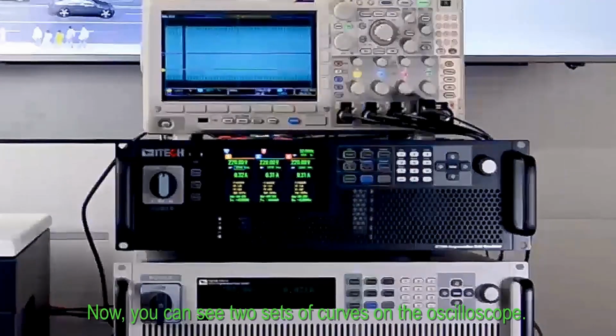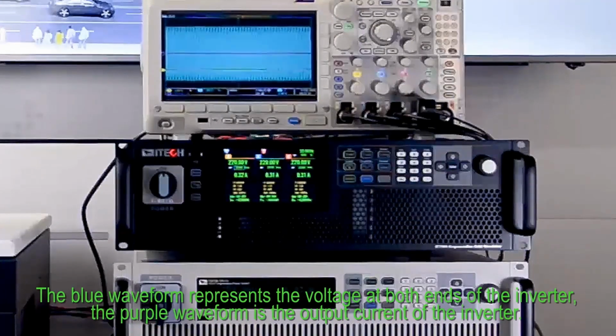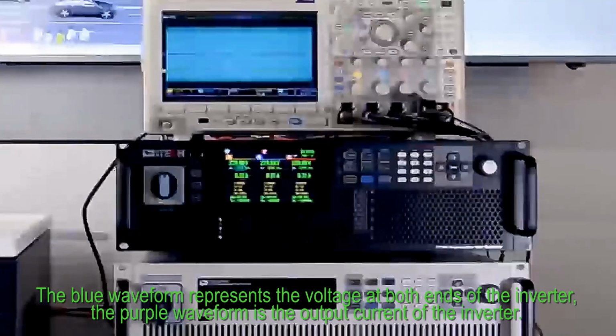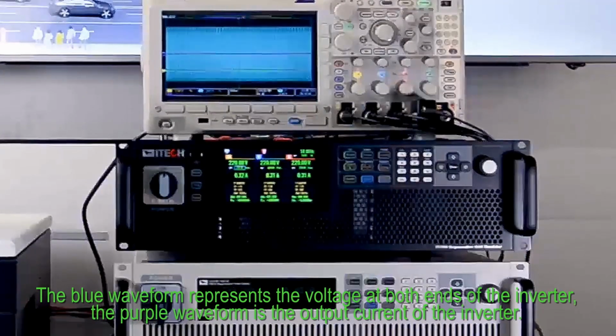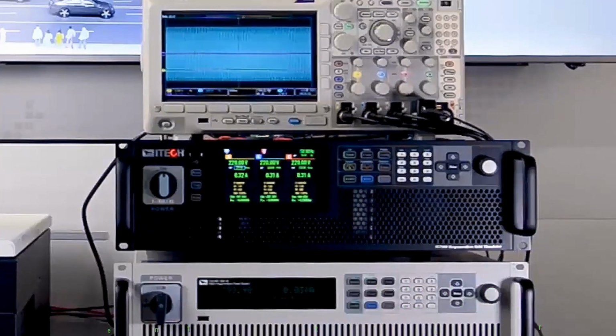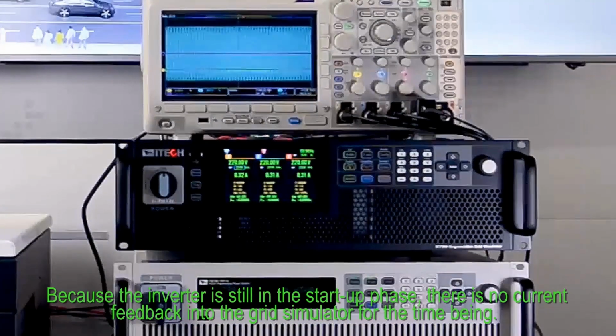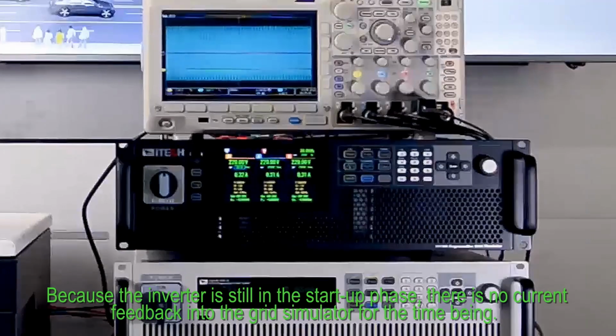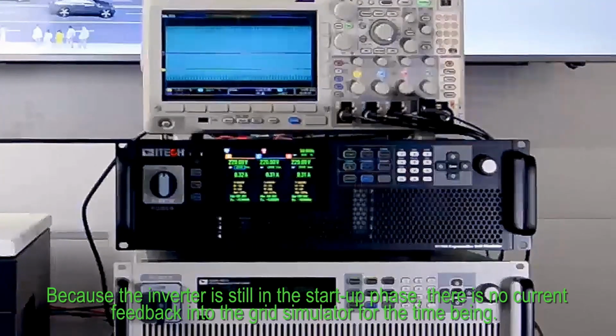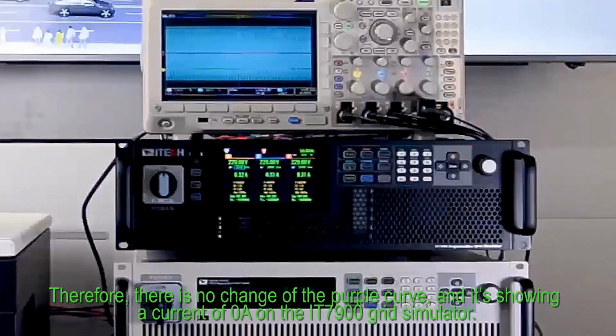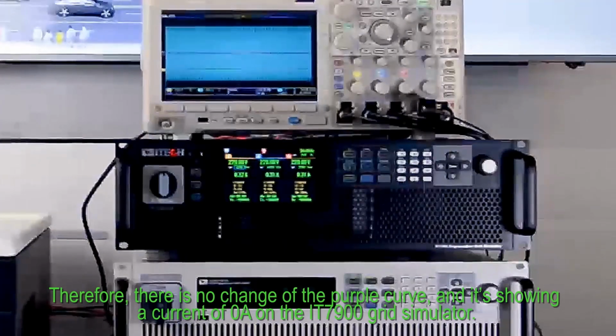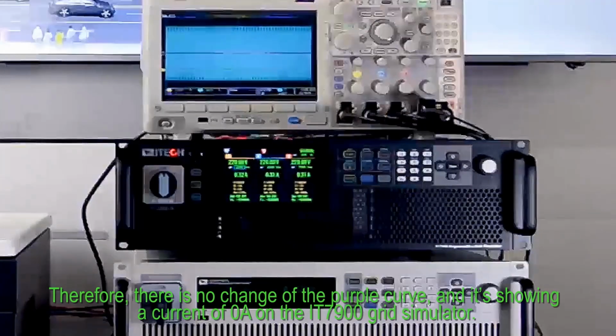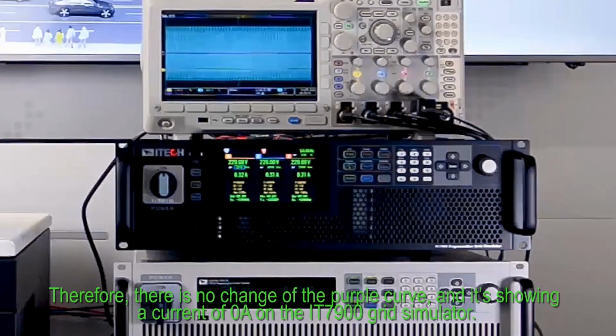Now, you can see two sets of curves on the oscilloscope. The blue waveform represents the voltage at both ends of the inverter, the purple waveform is the output current of the inverter. Because the inverter is still in the startup phase, there is no current feedback into the grid simulator for the time being. Therefore, there is no change of the purple curve, and it is showing a current of 0A on the IT7900 grid simulator.